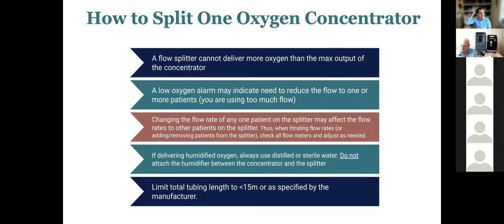Low oxygen alarm: if you're maxing out the unit, you may be using too much flow. It may start giving you some alarms with that. Changing the flow rate on any of the patients may affect the flow rates on the other patients on the splitter. So always check the flows for all the patients anytime you're adjusting the flows for any patient.